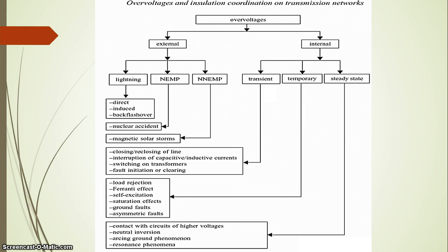Overvoltages are classified into external overvoltage and internal overvoltage. External overvoltages are caused by lightning — which may be direct, induced, or back flashover — and also by EMP from nuclear accidents, and geomagnetic solar storms, which also have the potential to induce overvoltages in the electrical grid.